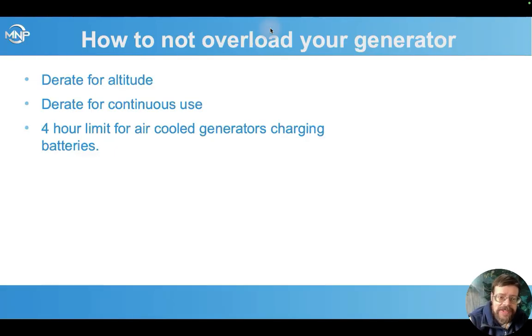When we're looking at generator sizing, we need to include a couple of derates versus the nameplate on the generator. Altitude's a big one if you're operating at higher altitudes. Where I worked a lot in Colorado, we were usually using a 30% derate for altitude, 9,000 feet and above. And that's a significant derate. Take a 15 kilowatt generator and suddenly it's really more like a 10 kilowatt actual output.